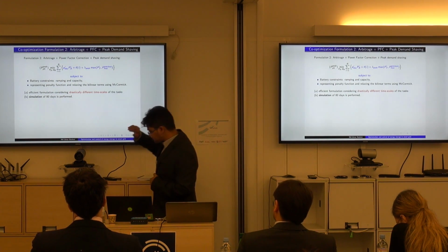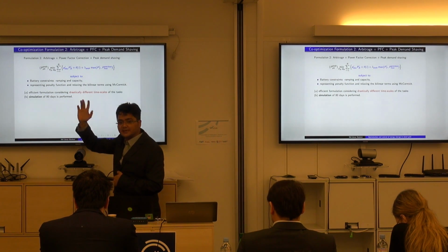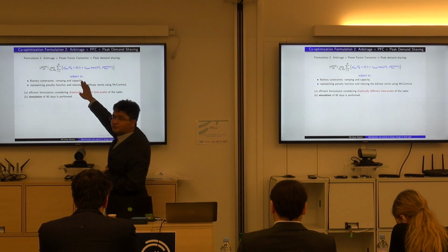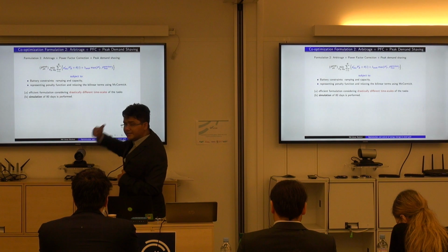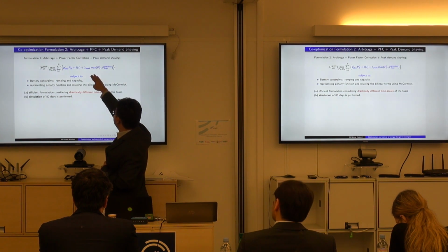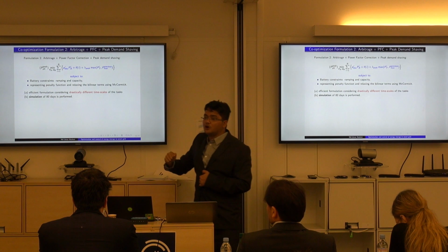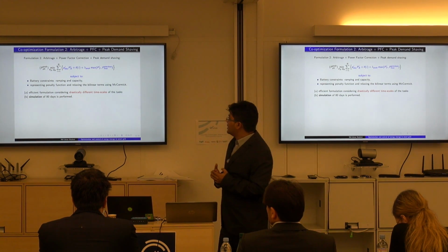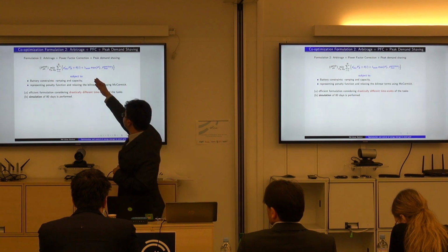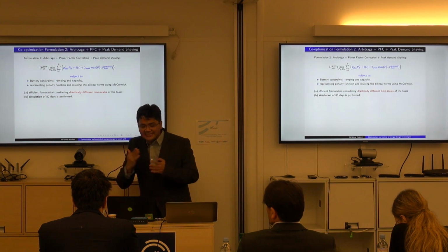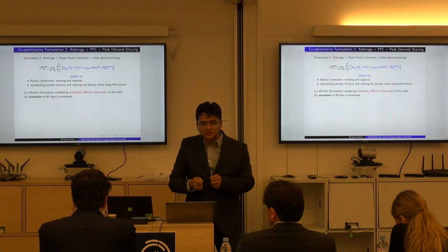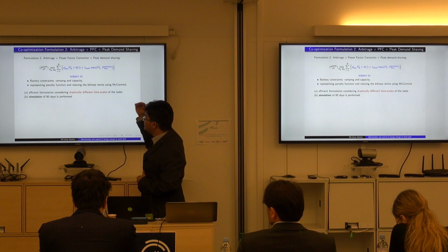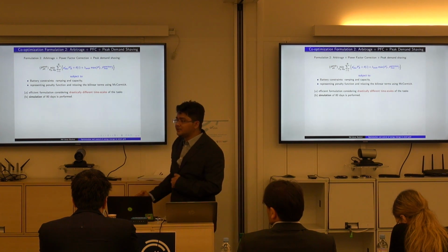In this case, the constraint remains the same as in the previous slide. So the first component is arbitrage, the second component is my penalty for power factor, and the third component here shows the peak component. Now the challenge is how do we deal with the different time scales, because peak demand charge is often applicable over a time scale of a month. So if we start solving this optimization problem for a month, it becomes intractable and we are not able to solve it.